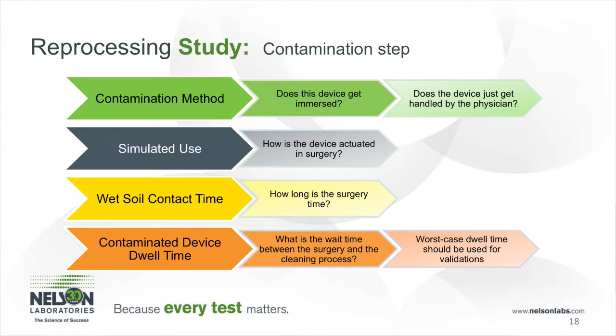The next thing, we need to make sure that the time that the device is in the test soil would be the exact time that the surgical procedure would be performed. And then the wait time after would be the amount of time that it takes for the device to get from the surgical procedure into the central processing area to be cleaned. Sometimes that could be a few minutes to hours, and sometimes it can be days if it's over a weekend time period.